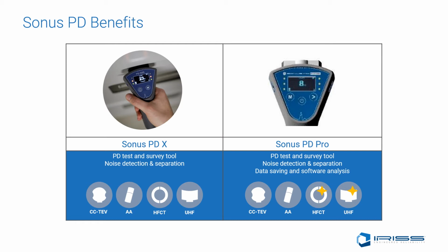Defects on the surface of a high-voltage insulator are prone to a phenomenon known as surface tracking. Tracking causes carbon deposits that build up over time, ultimately leading to flashover and insulation failure. The Sonus PD Pro and Sonus PDX detectors are highly sensitive to the ultrasonic emissions produced by tracking and enable early detection before insulation failure.